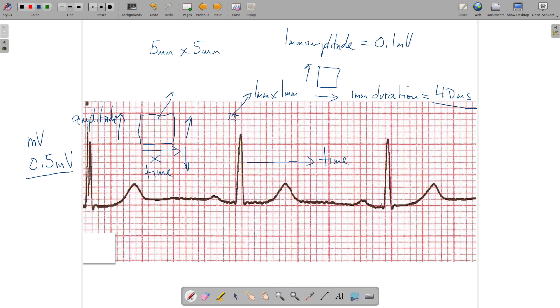Every time we have a deflection on the paper, we look at the number of millimeters it deflects. For example, if a big wave deflects 11 millimeters, we say 11 millimeters equals 1.1 millivolts, because every single millimeter of deflection up or down is representative of 0.1 millivolts of energy. So this waveform represents a 1.1 millivolt deflection, meaning the electrodes picked up 1.1 millivolts of energy from this person's body.